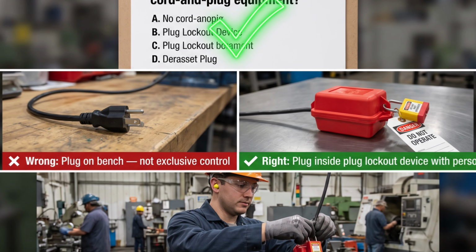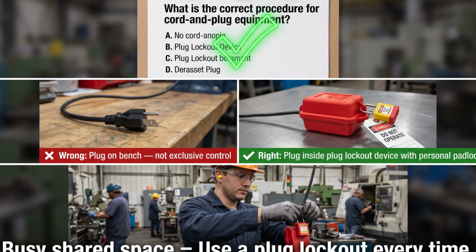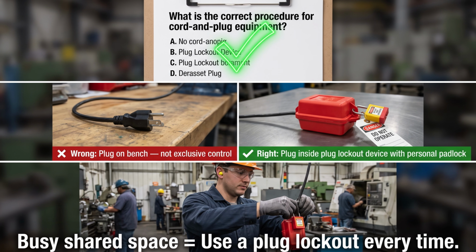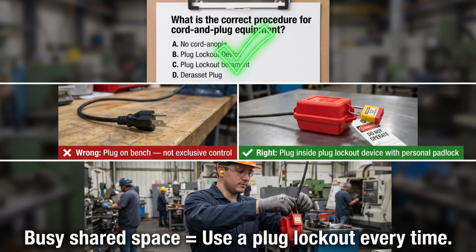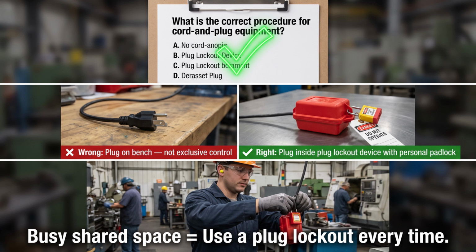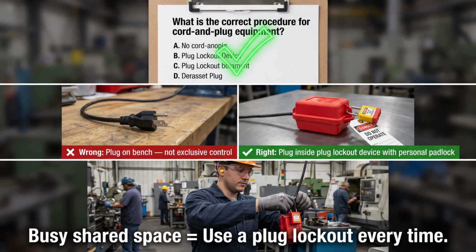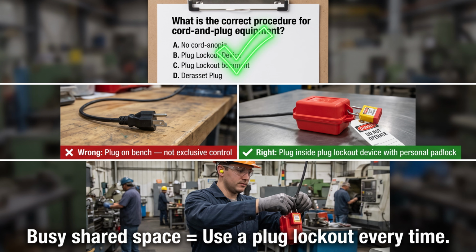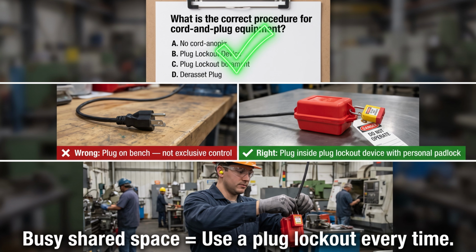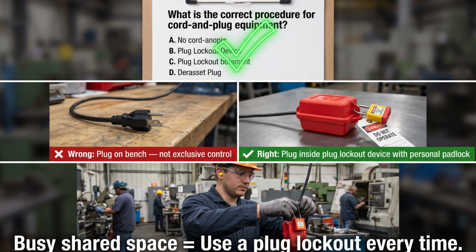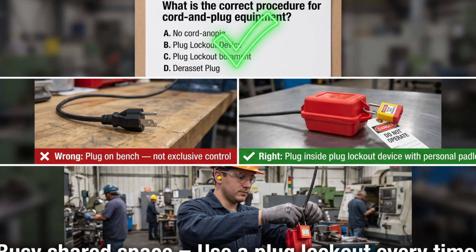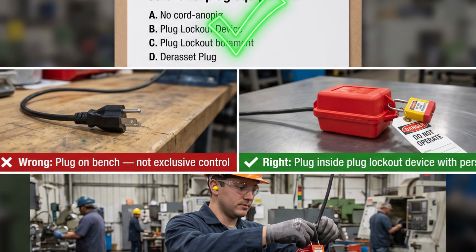Answer B. Placing the plug on the bench is not exclusive control. Anyone can pick it up and plug it back in. The tech should hold the plug personally or, best practice in a shared space, use a plug lockout device with their personal padlock. Being unplugged is only the first step, not the complete procedure. And if that grinder has any stored mechanical or electrical energy, those must be assessed too.